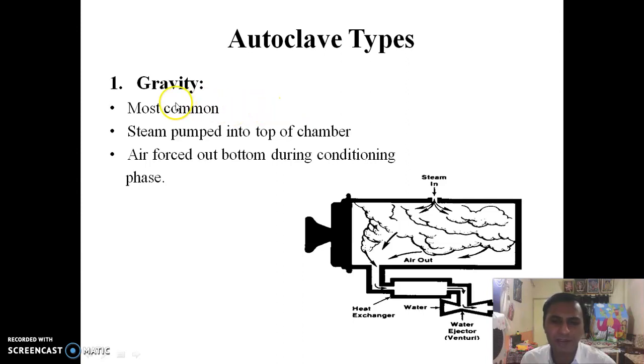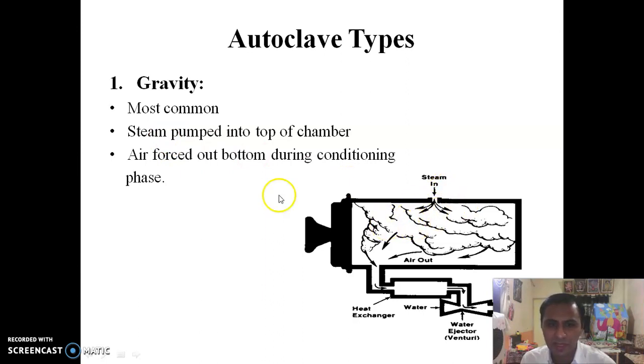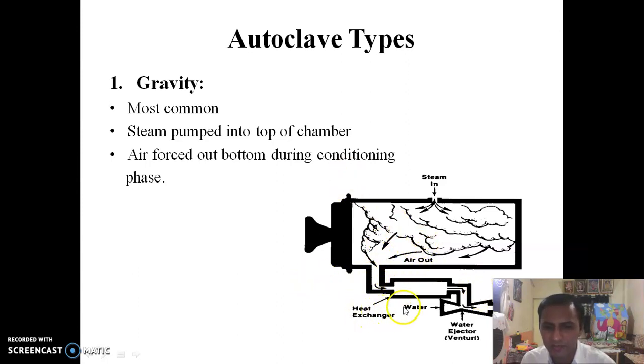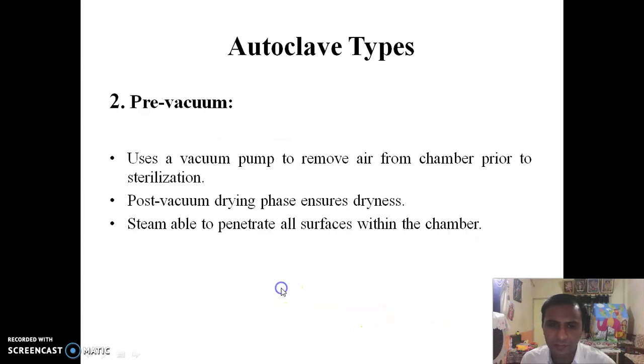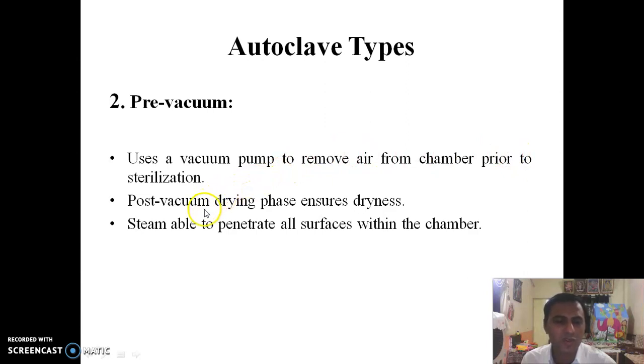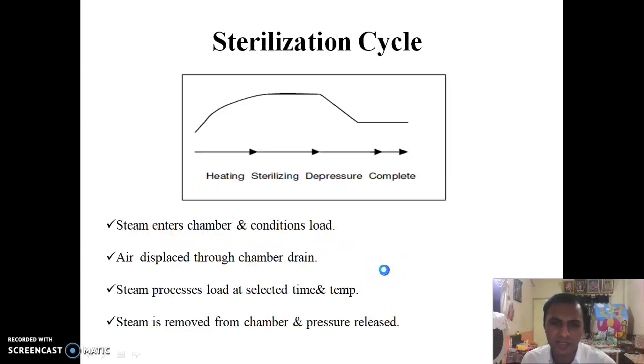There are two autoclave types. First, gravity displacement: based on the principle of gravity, most commonly used. Steam is pumped in at the top of the chamber and air is forced out at the bottom during the conditioning phase. Second, pre-vacuum type: uses a vacuum pump to remove air from the chamber prior to sterilization, with a post-vacuum drying phase to ensure dryness, allowing steam to penetrate all surfaces within the chamber.